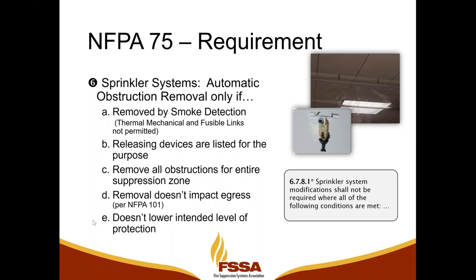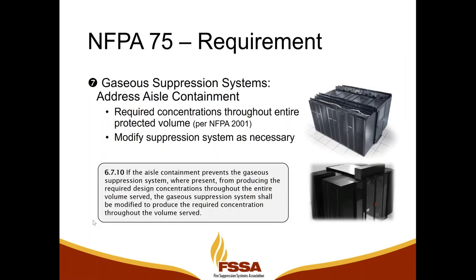So that's sort of a trade-off requirement that some data centers are choosing. Now, for gaseous systems, point seven is that the code says that gaseous suppression systems, where present, need to produce the required design concentration throughout the entire volume served, including the subvolumes for the contained aisleways. And you need to modify the suppression system as necessary to account for the aisle containment system.